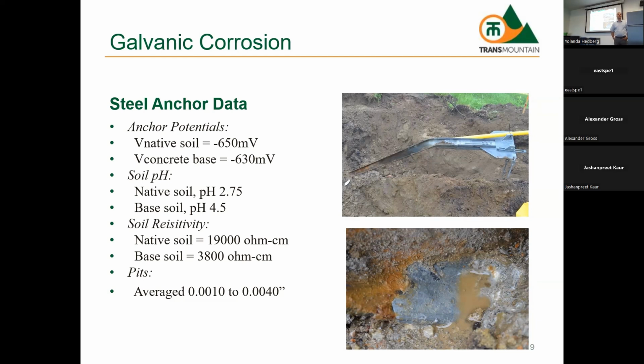I looked at the copper and asked the guy on site, where did this copper come from? I thought someone just threw some copper cable in the hole, because it looked brand new. So he's like, well, no, that was the ground cable wrapped around the concrete. I'm like, how long has it been there? Well, designed with the power.